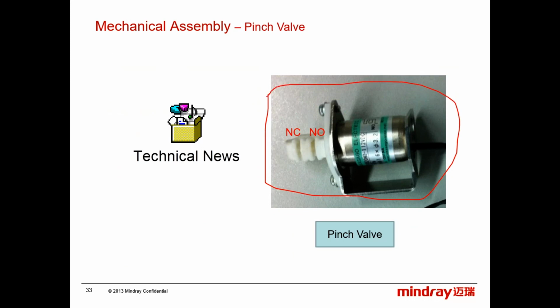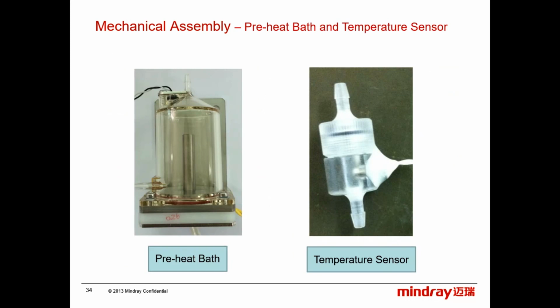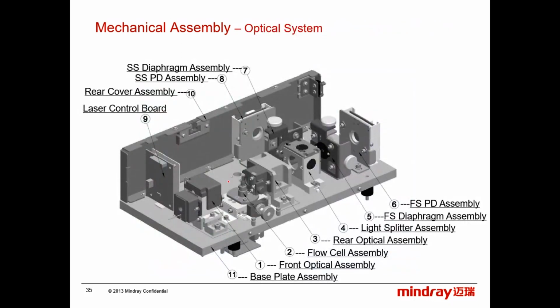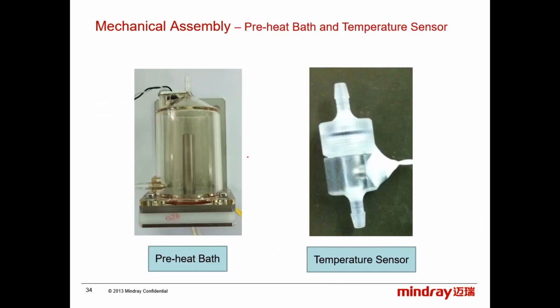Actually, before, we had a very high failure rate for this valve, mainly due to liquid spillage. But now we have another new type of this pinch valve. It is more robust, and we also added protection, like a metallic sheet. This is a pinch valve powered by a solenoid. This is the preheat bath for the diluent, and this is the temperature sensor.